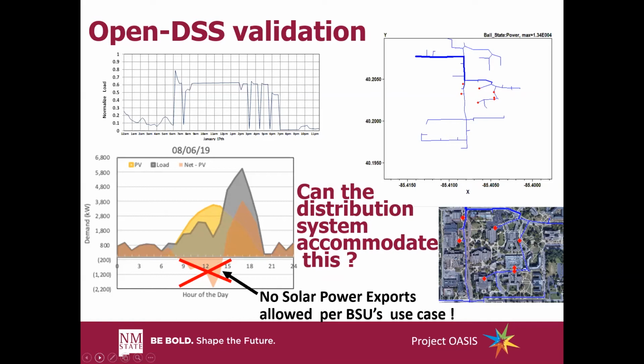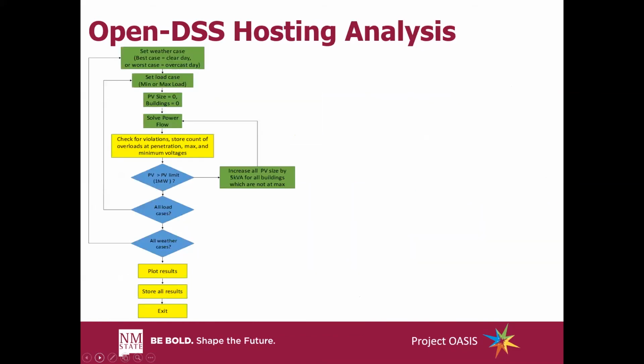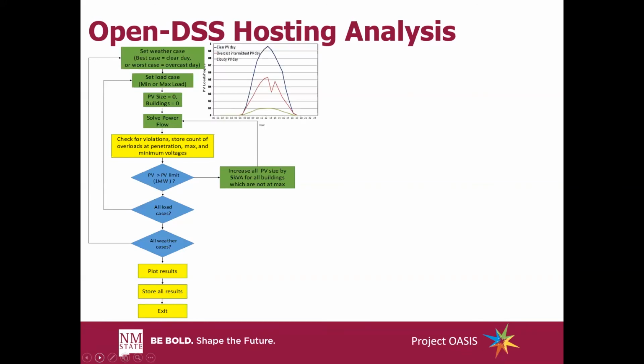The big question we need to answer is, can BSU's distribution system accommodate the PV systems and storage system we are proposing? Hosting capacity is defined as the maximum amount of PV that a feeder can accommodate before adverse impacts occur. This value will be dependent on the feeder, PV deployments, monitoring criteria, and load. The flowchart on the right shows a progression for performing the hosting analysis. These steps are as follows.